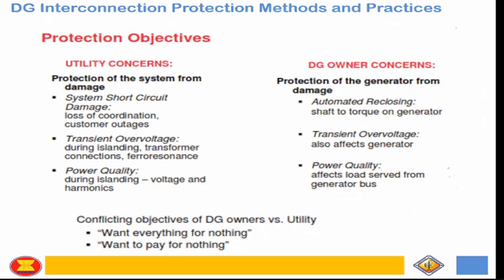So there's really a need of a distribution impact study. Kaya may distribution impact study tayo because of these potential concerns ng utility. And then the transient overvoltage during islanding, na-mention ko na kanina, if there's a mismatch between the generation and the load, hindi sila balanse. Okay, and then transformer connection and the ferroresonance, as mentioned kanina, there's a tendency during line-to-ground fault, if the ratio of the zero sequence impedance divided by the positive sequence impedance tataas, ferroresonance yung impact niya. Okay? And then also the power quality on the islanding, the voltage and the harmonics. Okay? So yun yung concern ng utility if papasok si DG or mga renewable energy natin sa distribution system.